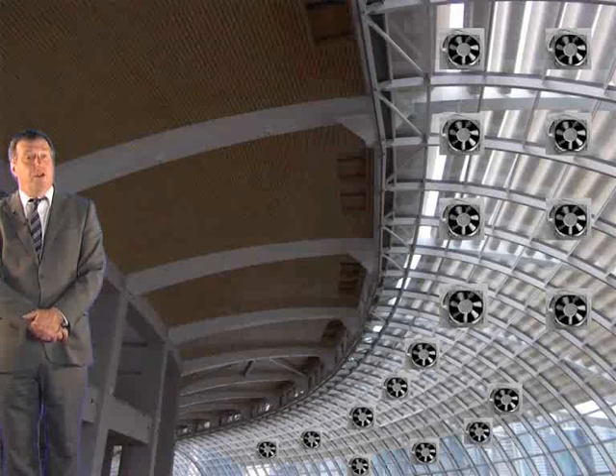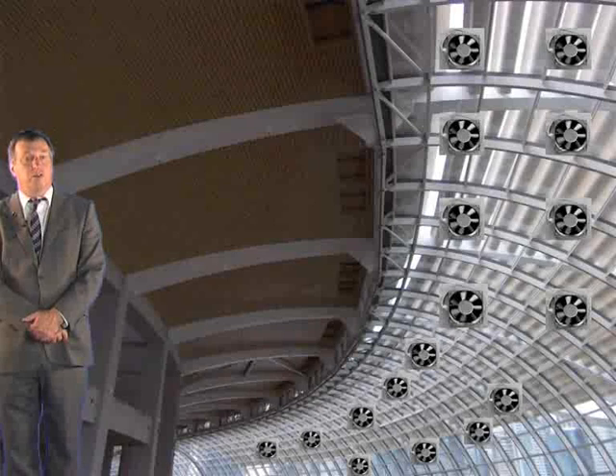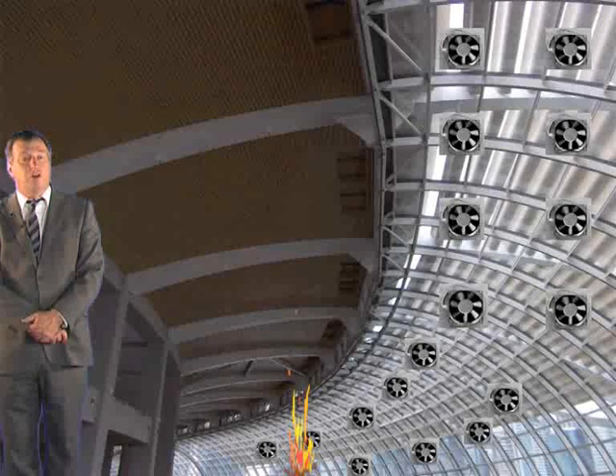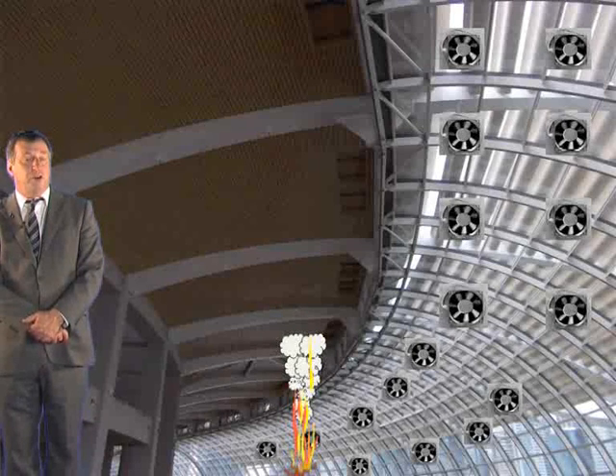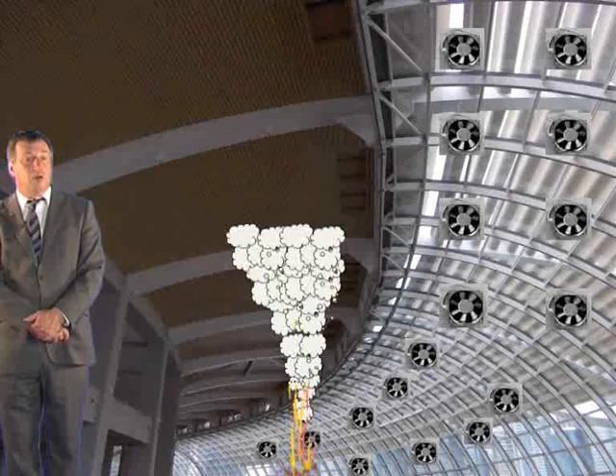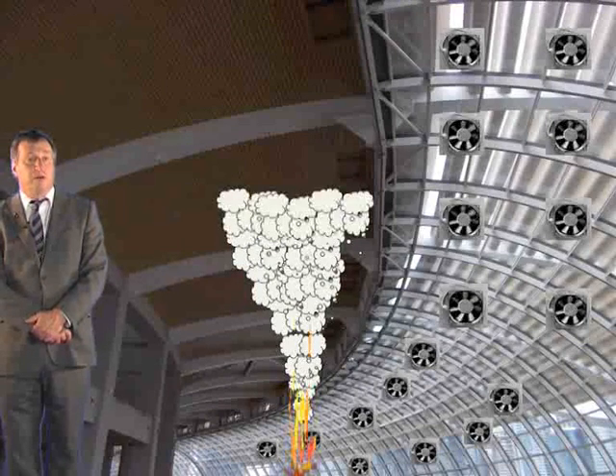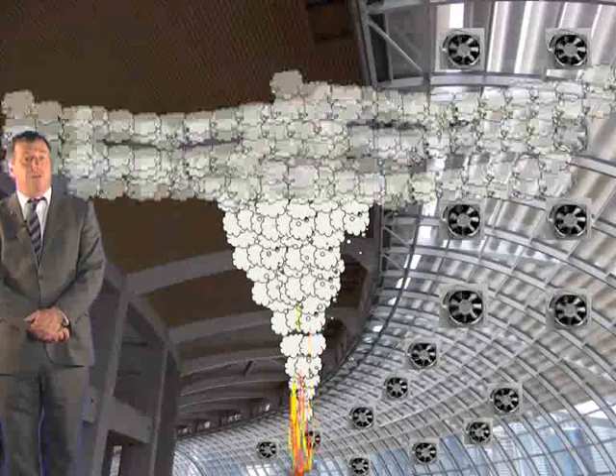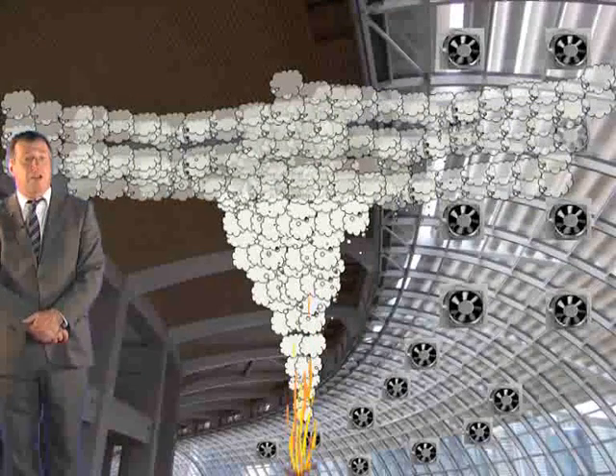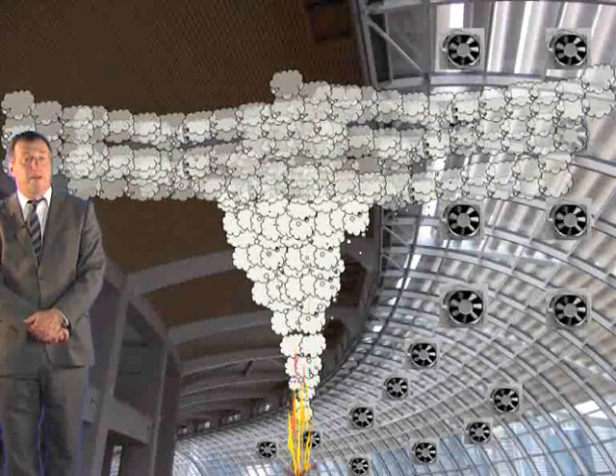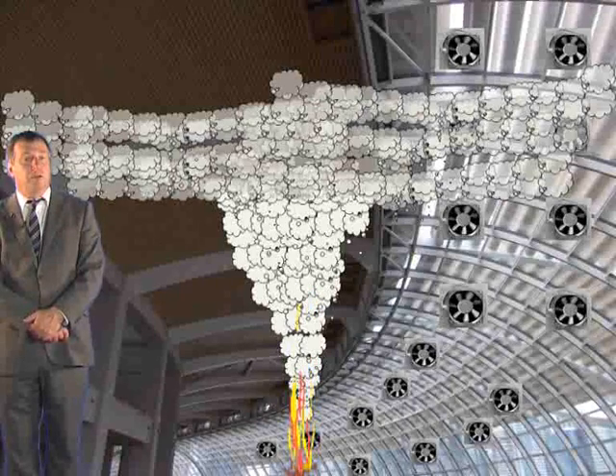Step 9, plug holing check. Now earlier we covered the principles of how many exhaust points are required, and this was based on the total mass flow rate of the smoke divided by the size or capacity of the exhaust points. If it was natural ventilation, the stagnation check had to be carried out. But now there's one more factor that must be considered.